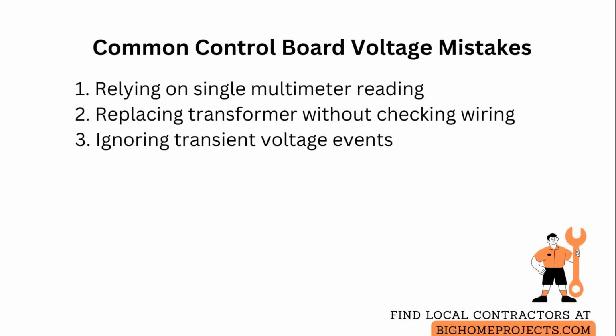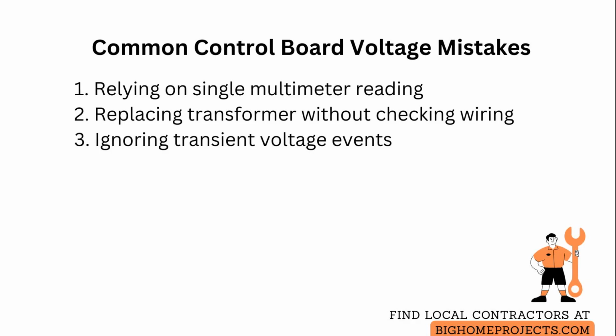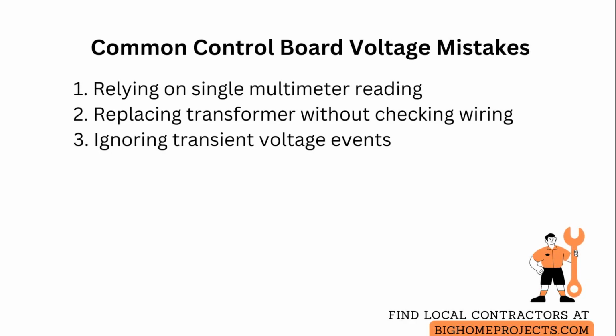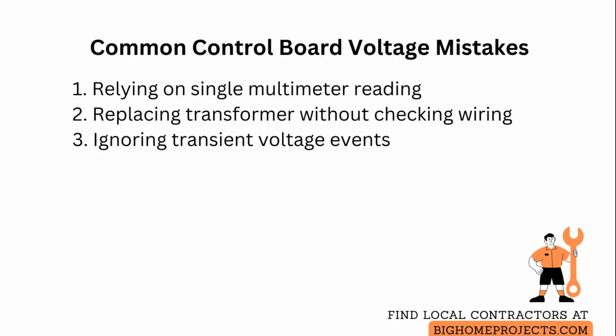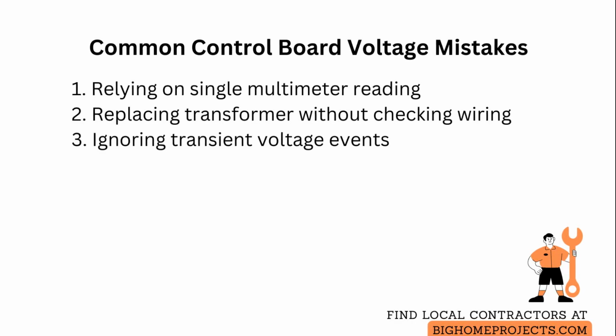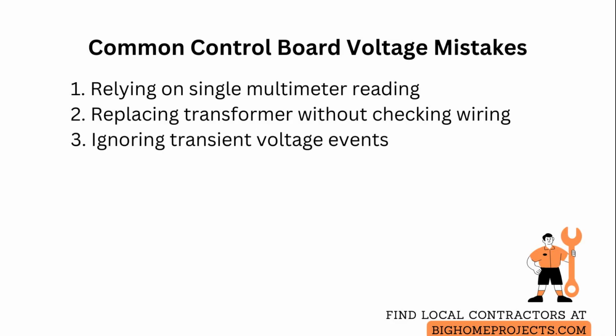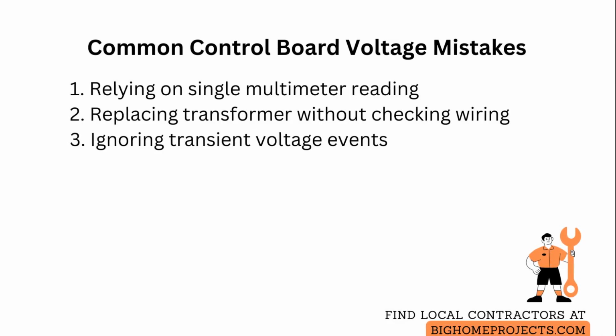Solution: measure both no-load and loaded voltages, and perform voltage tests under expected operational load to reveal regulation issues. Another mistake is replacing the transformer without checking wiring resistance and connections. Solution: measure conductor resistance and inspect all terminals first, since correcting wiring or tightening connections often resolves low voltage symptoms without replacing hardware.